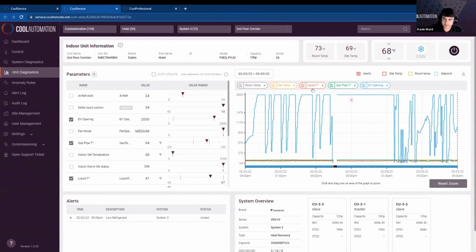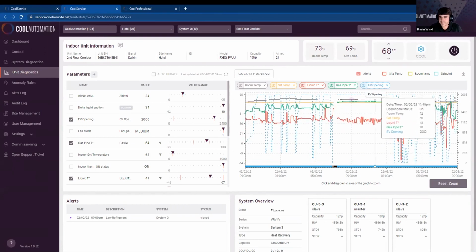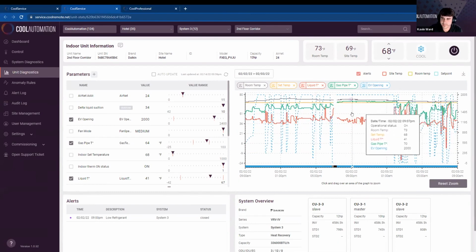So the room temp, the set temp, liquid and gas, and the valve position. Again, adjusting this so that everything fits nicely on the graph. We can see here that each of those different conditions have been satisfied. We can see a 30-degree delta across the coil, a 5-degree difference between the set point and the room temp, and that valve position wide open. So leveraging the anomaly rules would have allowed us to catch this system error, the low refrigerant, a week prior to the system actually failing on its own.